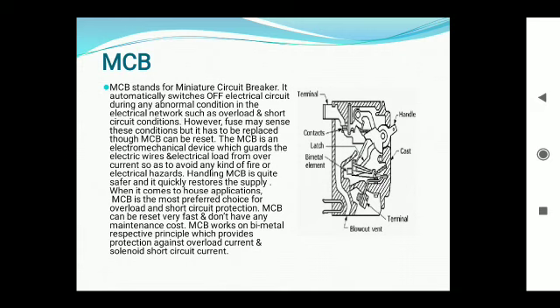Handling an MCB is quite safe and it quickly restores the supply. When it comes to house application, MCB is the most preferred choice for overload and short circuit protection. MCB can be reset very fast and doesn't have any maintenance cost. MCB works on the bimetallic principle, which provides protection against overload current, and a solenoid for short circuit current.